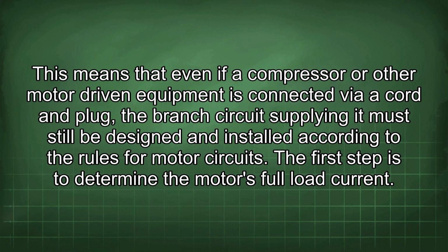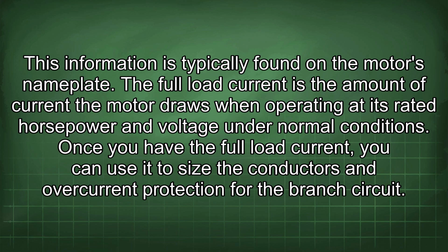The first step is to determine the motor's full load current. This information is typically found on the motor's nameplate. The full load current is the amount of current the motor draws when operating at its rated horsepower and voltage under normal conditions. Once you have the full load current, you can use it to size the conductors and overcurrent protection for the branch circuit.